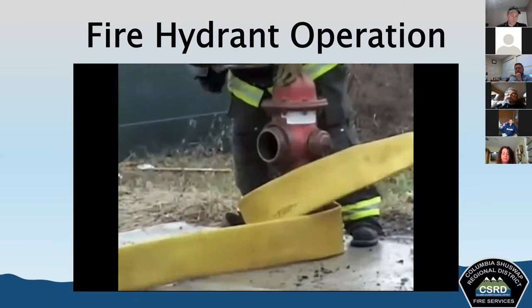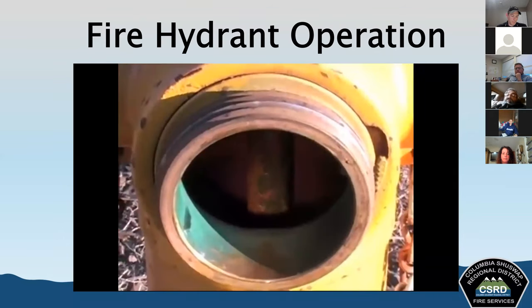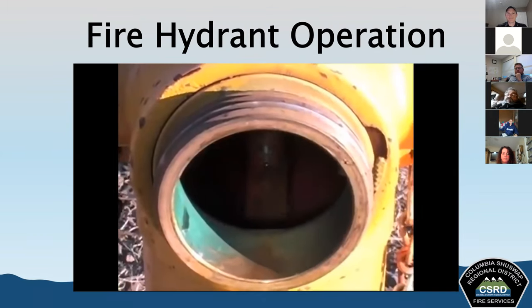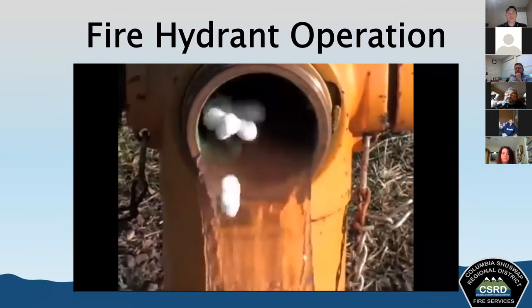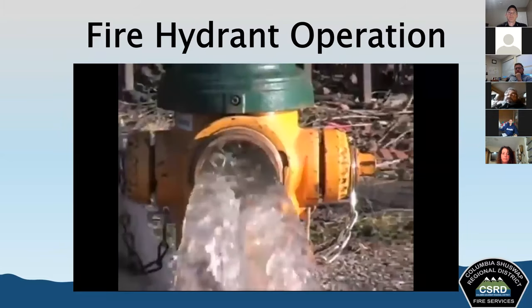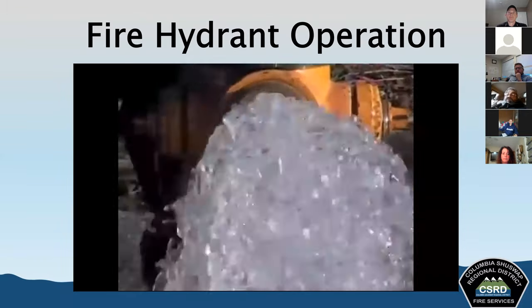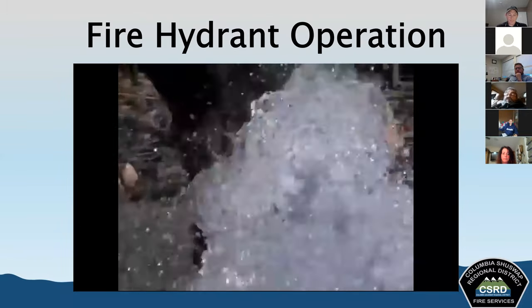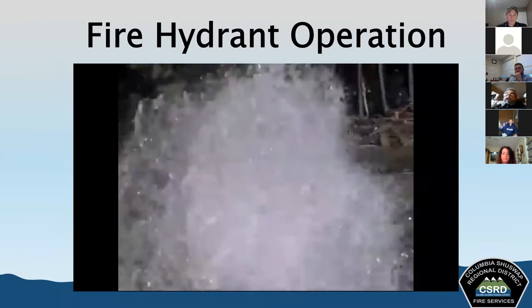Lefty loosey. Turn the stem slowly. The water should gradually move up the barrel. This will help clear the hydrant of debris. Now, turn the stem until it is fully open. The discharge force should be noticeably greater. If it isn't, notify your officer.